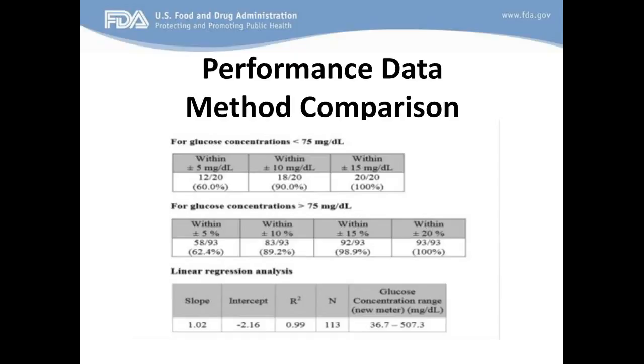We look to see how well it is within 5% of what the value should be, within 10%, 15%, and 20%. We find that particularly for over-the-counter glucose meters, describing the data in this way is helpful to people who use it. It gives you an idea of the variability and the accuracy of the test. Finally, we look to see how well the meter performs against a standard reference, and we do that by doing a correlation, looking at the slope and the intercept, and it gives you an idea of how accurate the meter is.